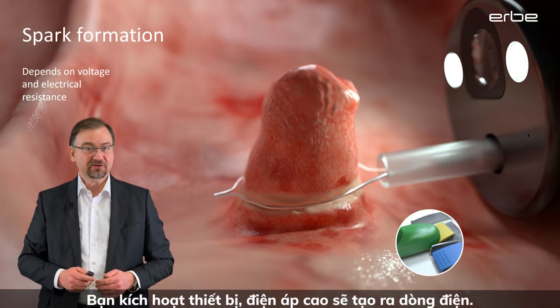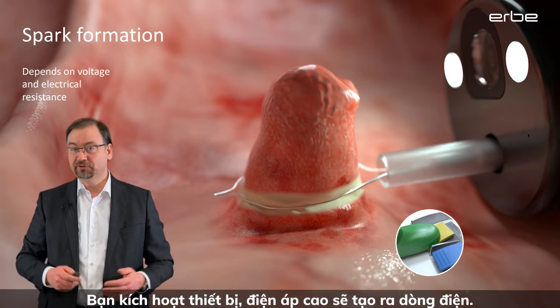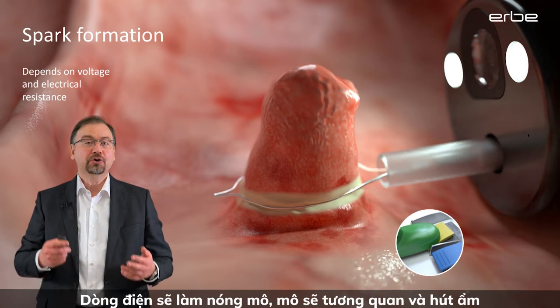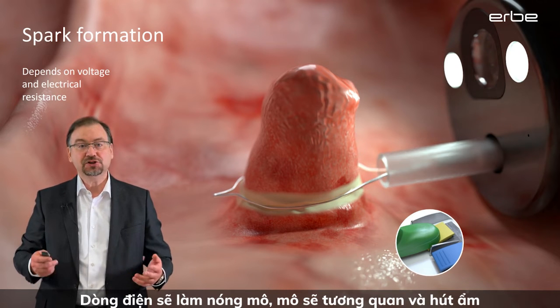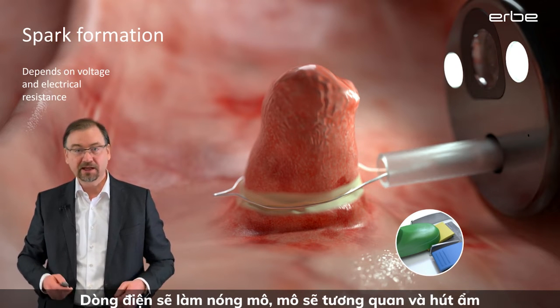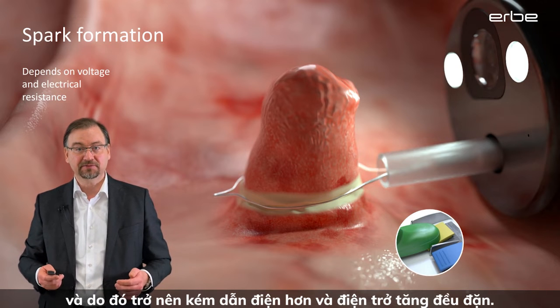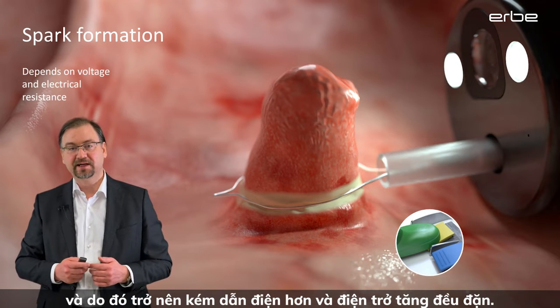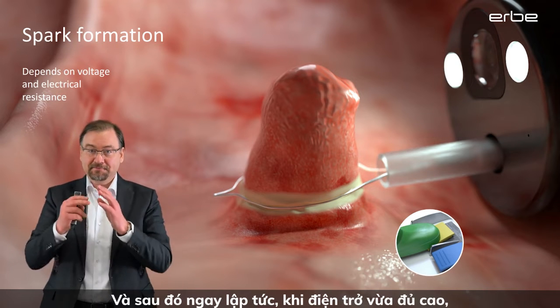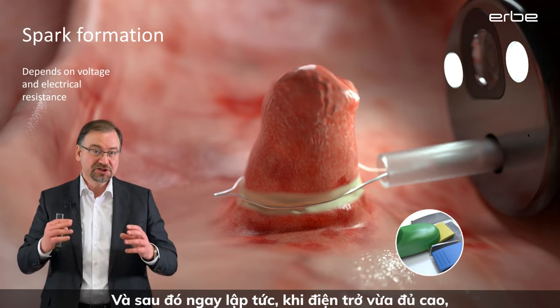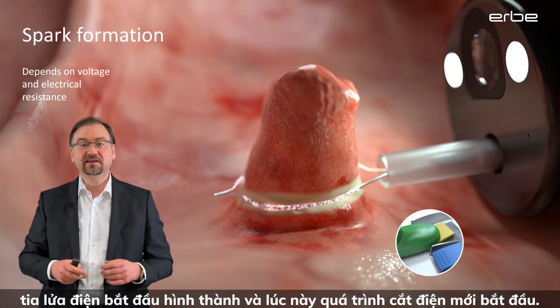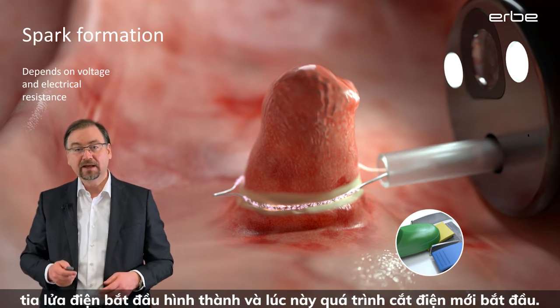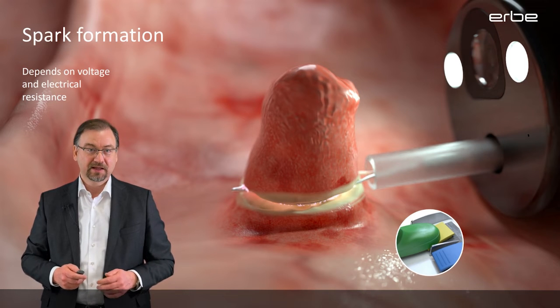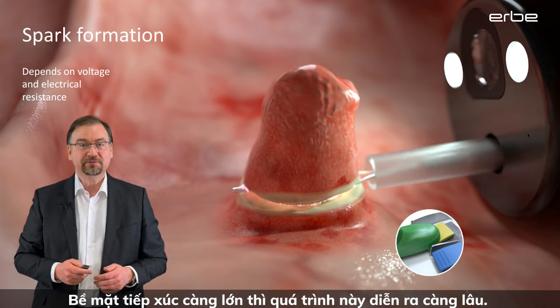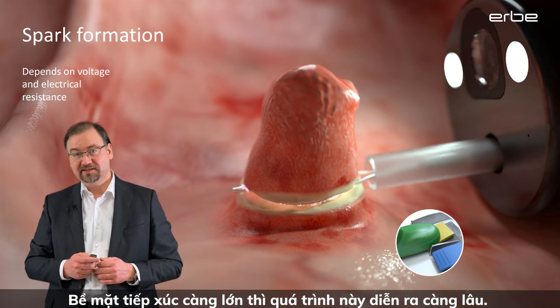You activate the instrument, the high voltage will produce electric current, the current will heat up the tissue, the tissue will coagulate and desiccate, and thereby becomes less conductive, and the resistance steadily rises. And then, in the very instant when the resistance is just high enough, the sparks start to develop, and only now the electric cutting begins. The bigger the contact surface is, the longer this process takes.